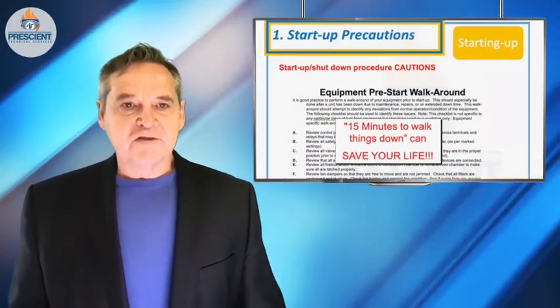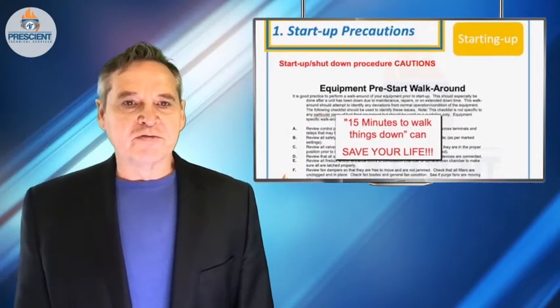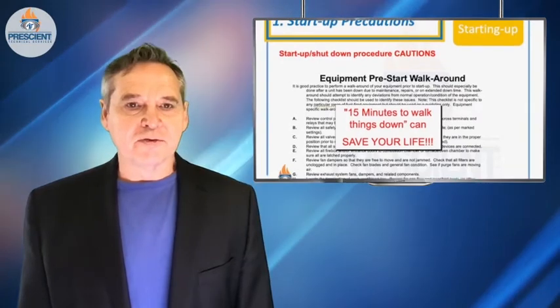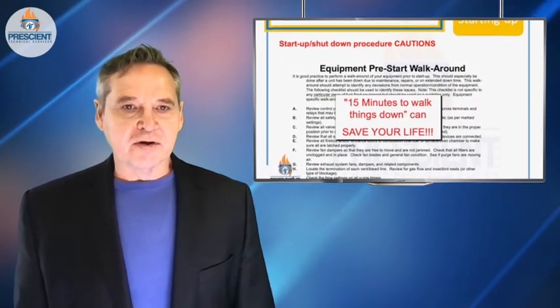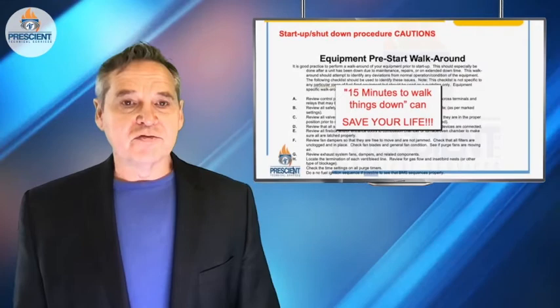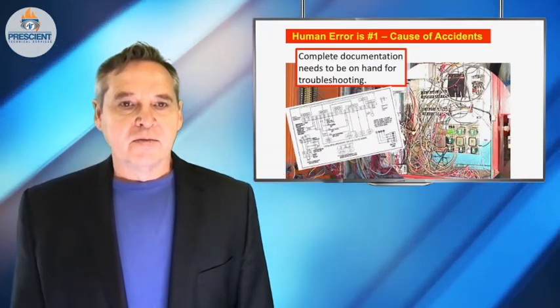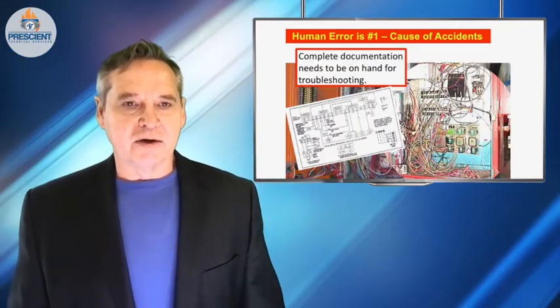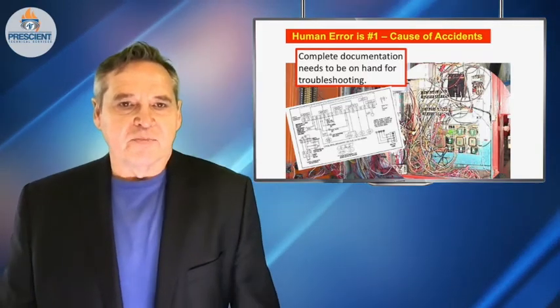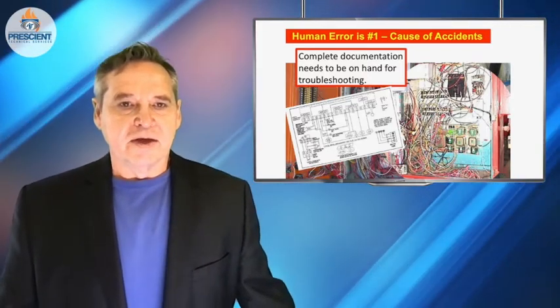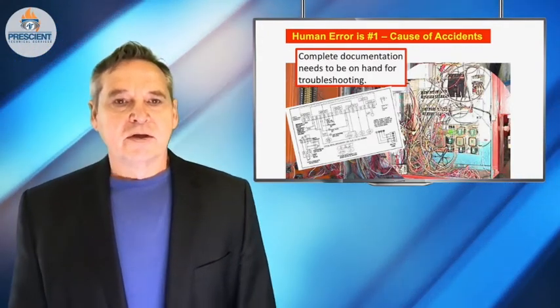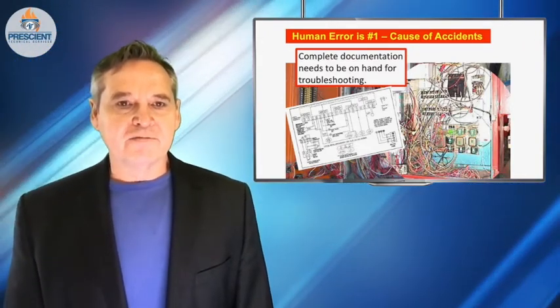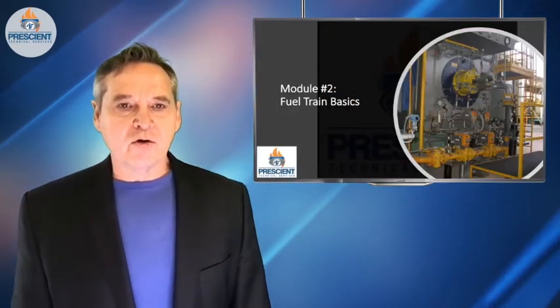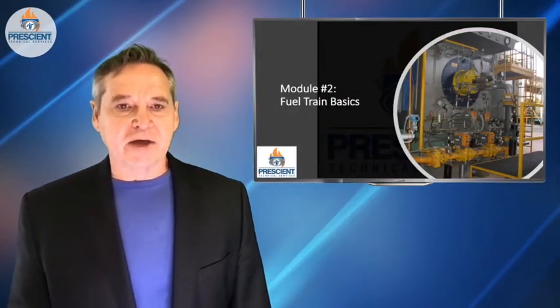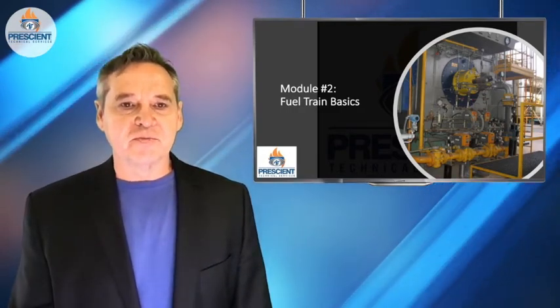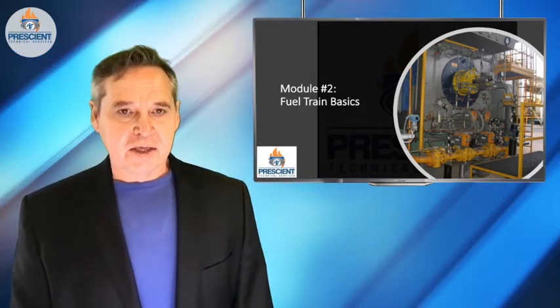It's been my experience that some of the most vulnerable times of operating fuel-fired equipment are when you're starting something up or when someone's troubleshooting that equipment, possibly because it wouldn't light off. It's very rare things are just operating fine and then all of a sudden they turn into a tragedy and explode. No, most often it's a light off or some troubleshooting event. Want to know more about how to recognize some of the hazards associated with starting up systems and troubleshooting them? Keep watching.